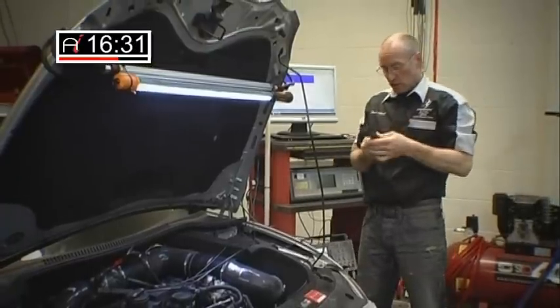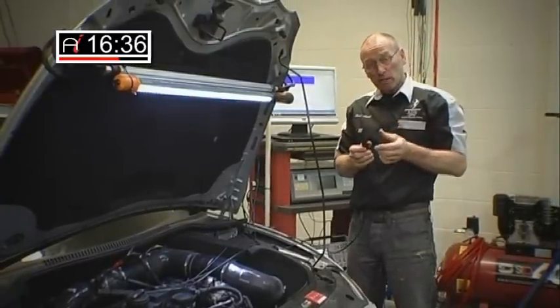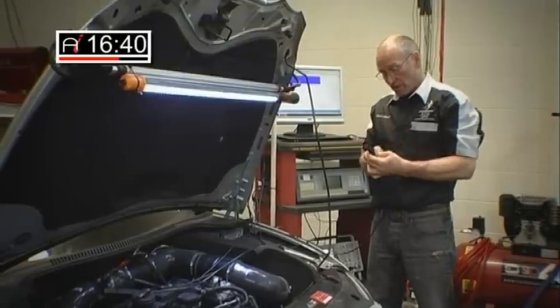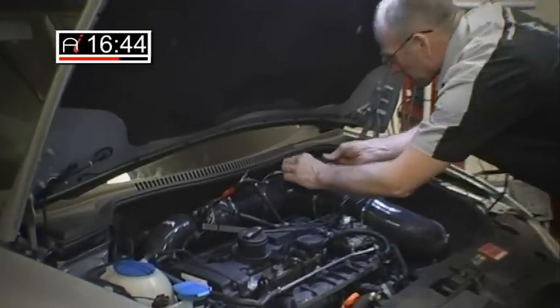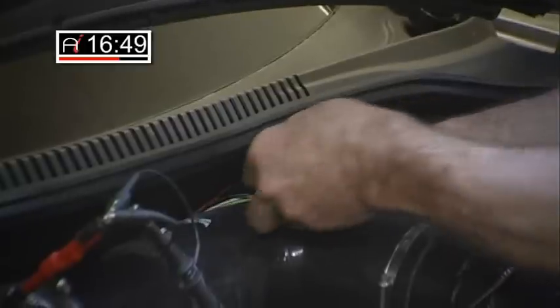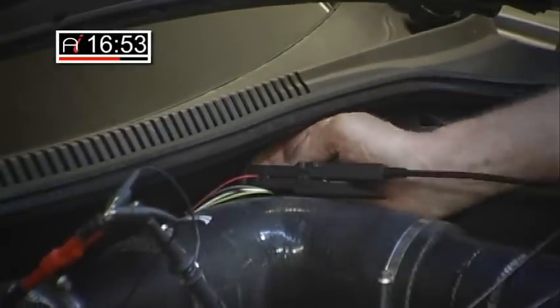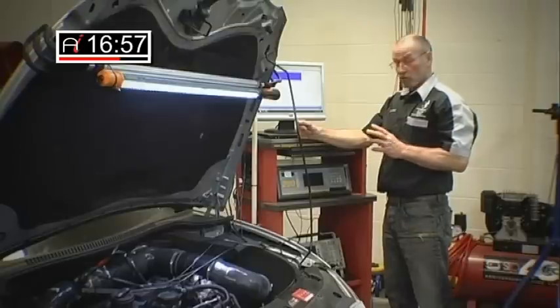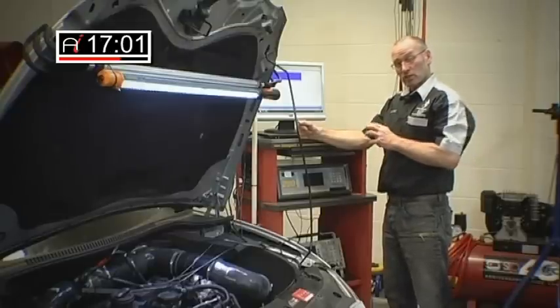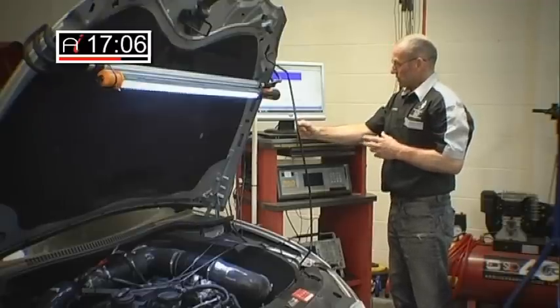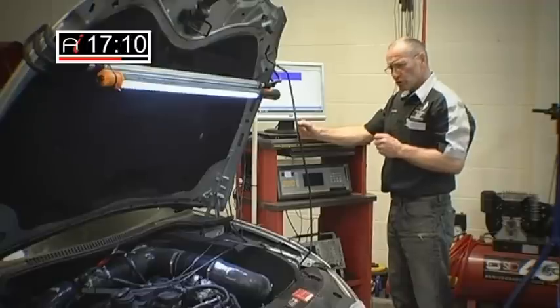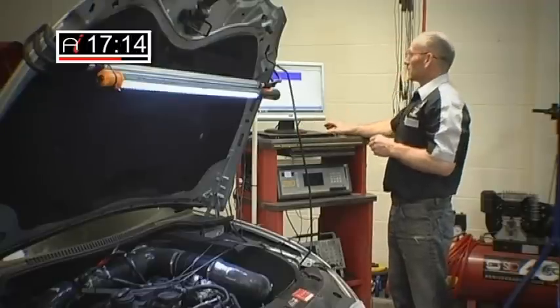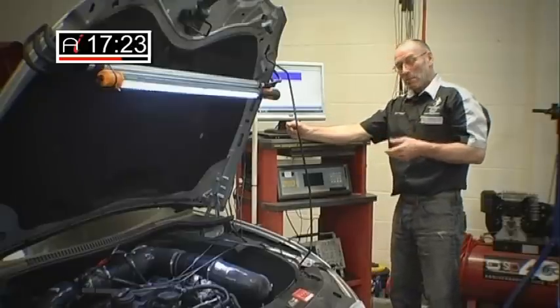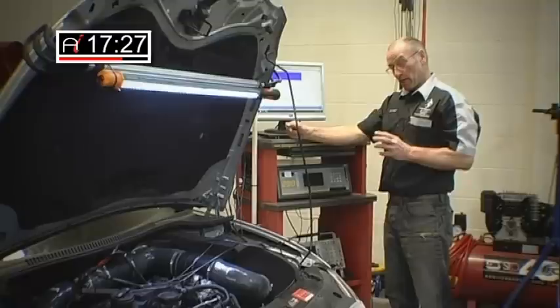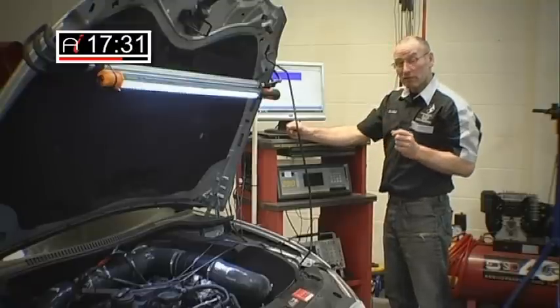Both probes connected. So this probe now goes on the signal cable of the lambda sensor, which is the red or pink cable, with the arrow in the direction of the device, which is to my left. Goes completely around the cable, making sure the jaws are completely closed. Now that the connection has been achieved, we need to convert the range on the scope to convert current into an analog image. And we have found that a range of around 200 millivolts should produce a reasonably responsive signal size. So I'm going to change channel 4 to 200 millivolts. That gives us a 20 milliamp range. I'm only expecting about 5 milliamp deviation, so I may actually change that to 100 millivolts, which is a 10 milliamp range.